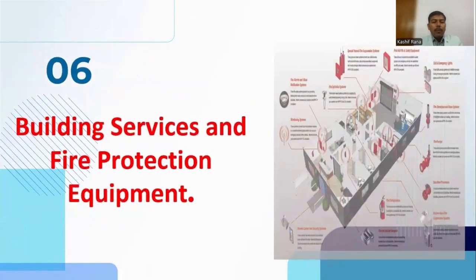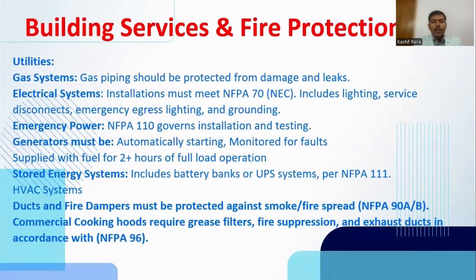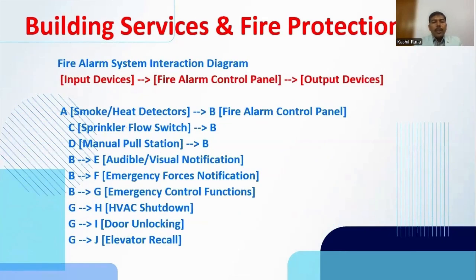Building services and fire protection equipment are an overview of the building management system. We will discuss in later sessions that for design, we must consider the utilities in the building like gas supplies, electrical supplies, power backup, and secondary stored energy systems. Ducts and fire dampers must be protected against smoke and fire spread. We'll discuss the fire alarm system interaction diagram for the building management system. It is based on 3 devices: input devices, the fire alarm control panel, and output devices. The input devices initiate the signal and pass it to the control panel, and on receiving the signal, the control panel directs the output devices for different functions.